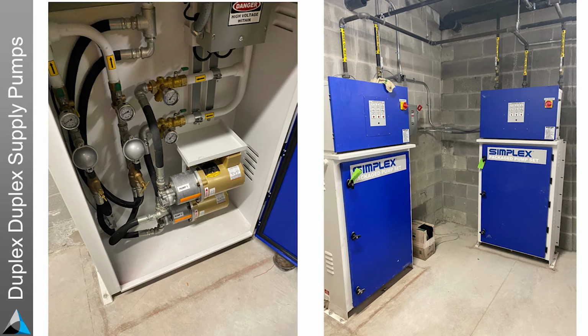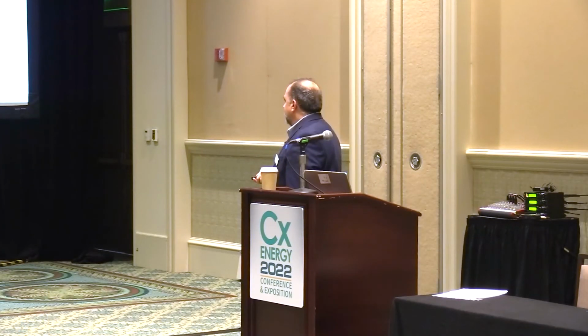So I open them up and check to make sure the motors work and all that. I'll talk more about that in a second. But that's what I was expecting to see: two duplex pump sets, and a fuel polisher, fuel cleaning system. It basically cleans the fuel as it goes from the supply tank out to the generator, so we've got clean fuel. Fuel quality is an important issue.